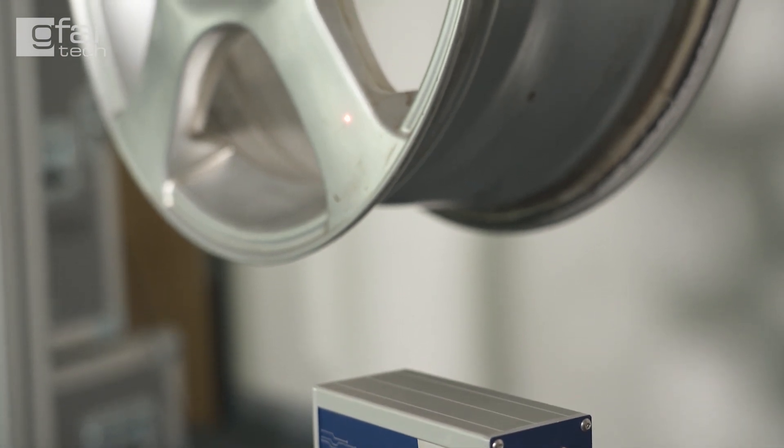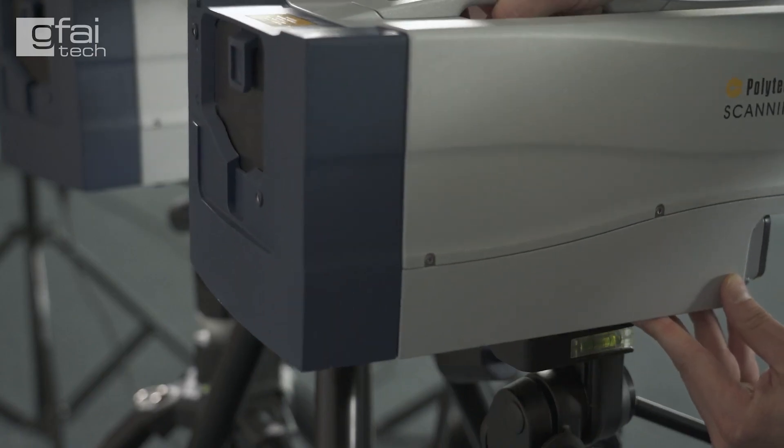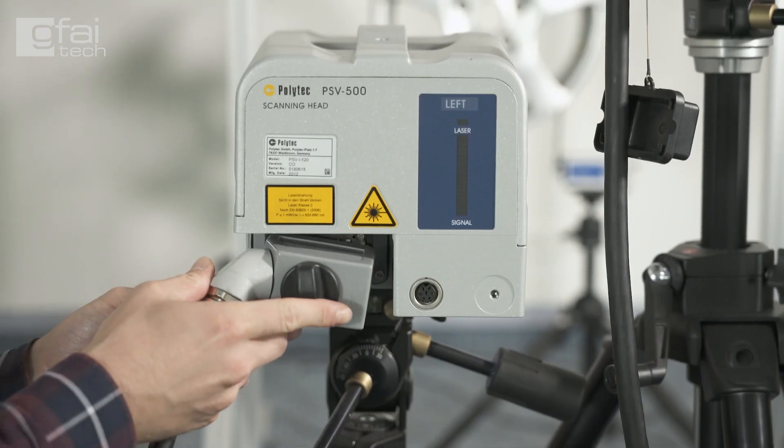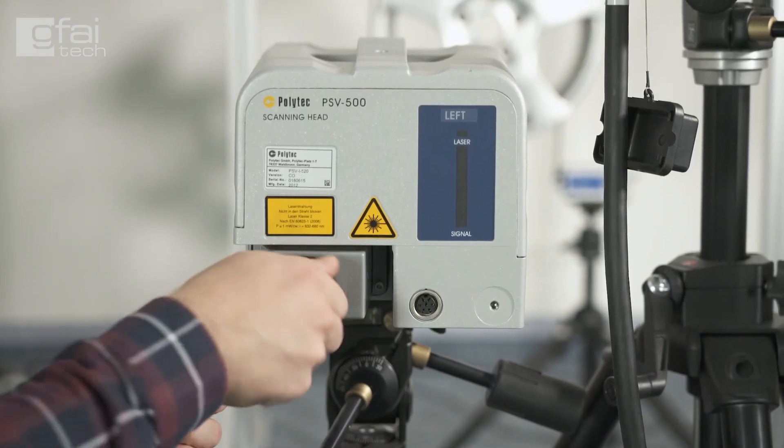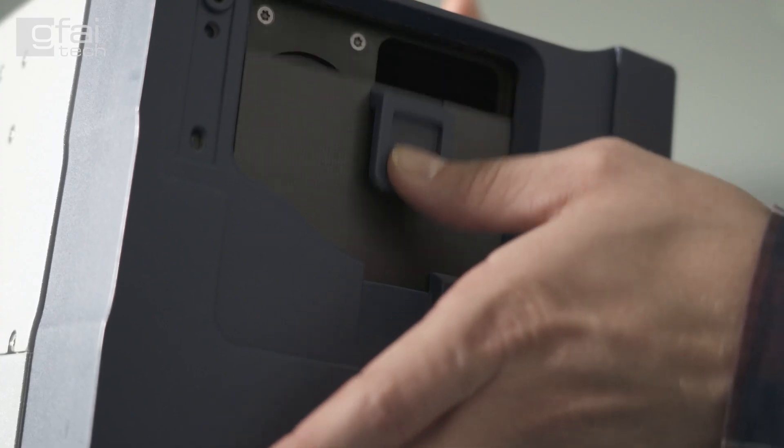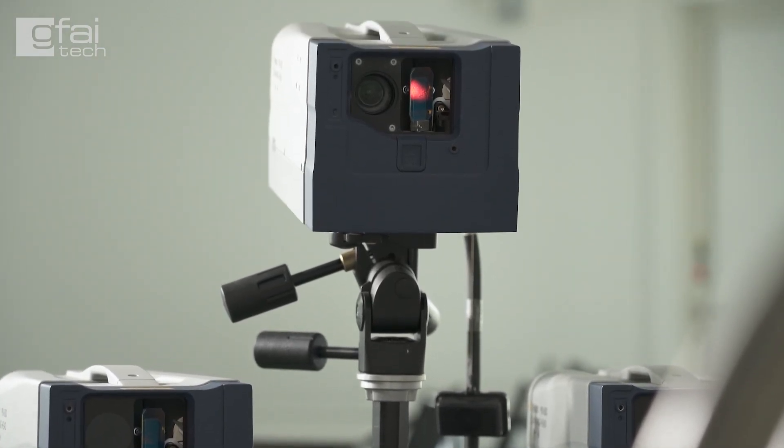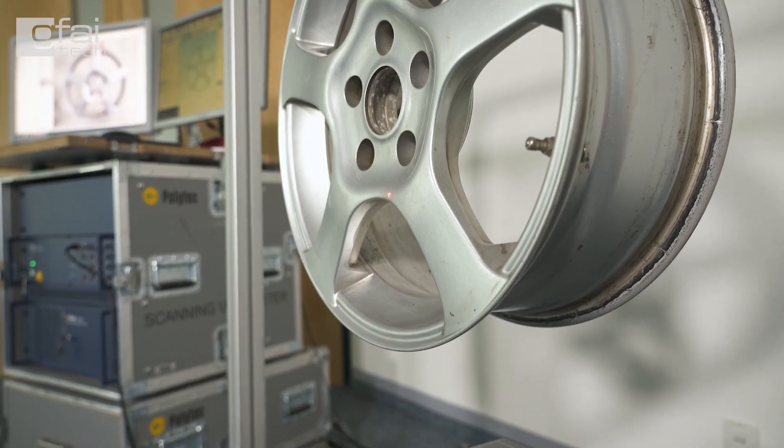Three laser Doppler vibrometers measure the response of the structure's excitation to get the information from all three dimensions. The main benefit of using this laser system is that it is a non-contact type of measuring, so no additional mass loading of attached sensors which could influence the results.